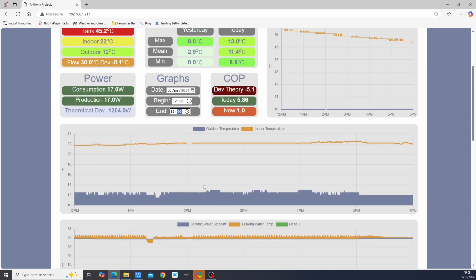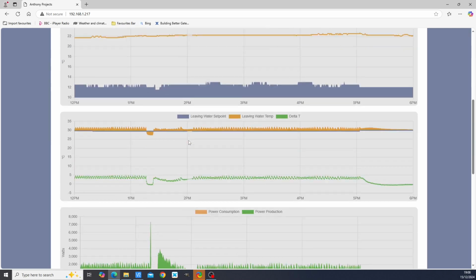And of course, the consequence will be that your heat going into your system would increase, which would warm up your house even faster. And it will warm it up to the point where it cuts out at 22.5 degrees. And that's probably going to be the way you need to do it. So weather compensation curves are not as straightforward as you imagine.